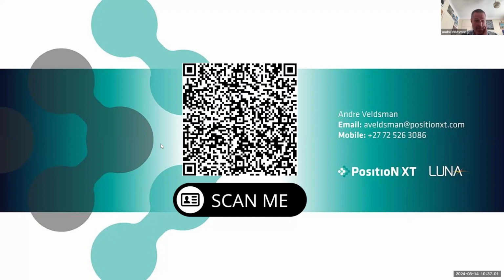Okay. It's a follow-up on the previous one. So in ultra deep mines, the depth is an issue for the barometric pressure and air density. Will you be able to calibrate it yearly at the installation site as per the new mandatory code of practice? Yes, because calibration for us would really be just reference checking. We do not have to take out the equipment and send it back for recalibration. Because we are measuring the absolute temperature along the fiber, we do have a protocol in place where there are reference points along the installation, which we do verification checking on and see that we are within a certain percentage of the actual ambient temperature compared to what the fiber optic cable is measuring. We do have the capability within the software to then adjust the threshold, but in general, yes, we would be able to calibrate on site.